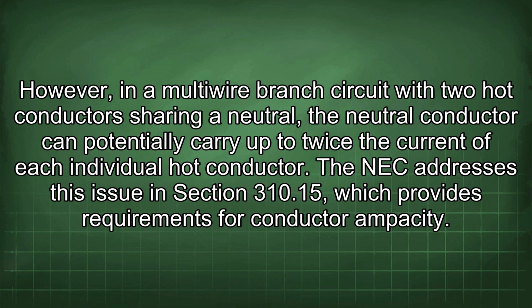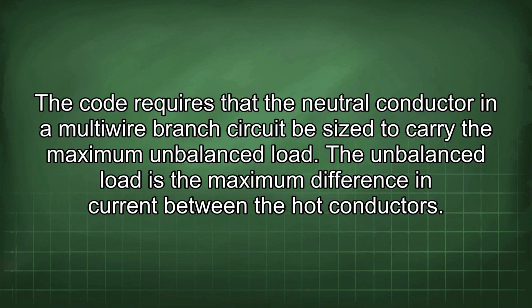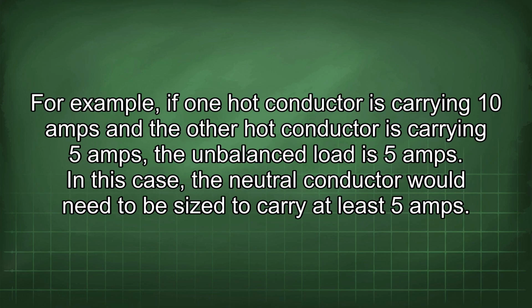The NEC addresses this issue in section 310.15, which provides requirements for conductor ampacity. The code requires that the neutral conductor in a multi-wire branch circuit be sized to carry the maximum unbalanced load. The unbalanced load is the maximum difference in current between the hot conductors. For example, if one hot conductor is carrying 10 amps and the other hot conductor is carrying 5 amps, the unbalanced load is 5 amps. In this case, the neutral conductor would need to be sized to carry at least 5 amps.